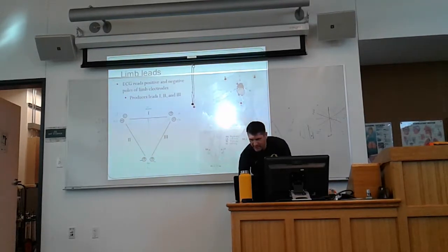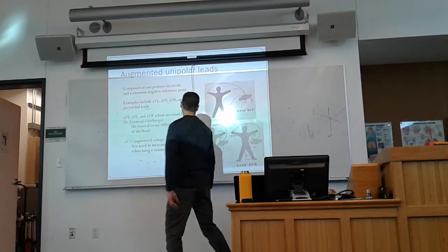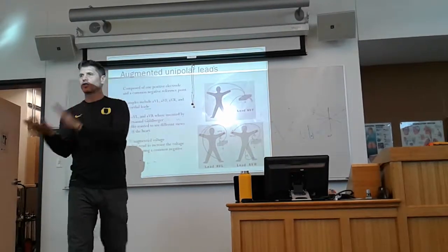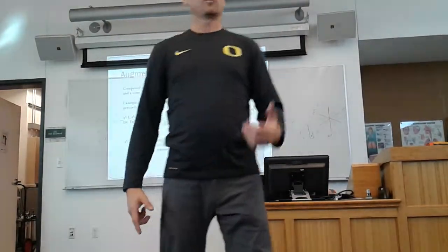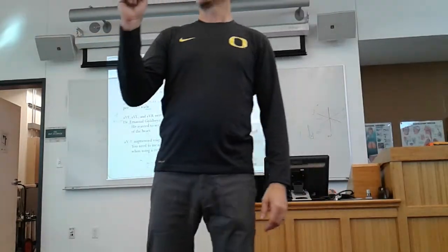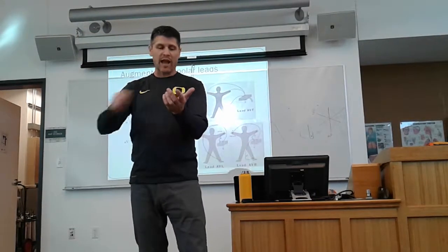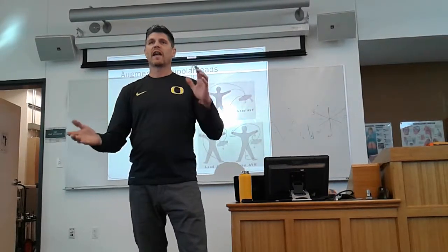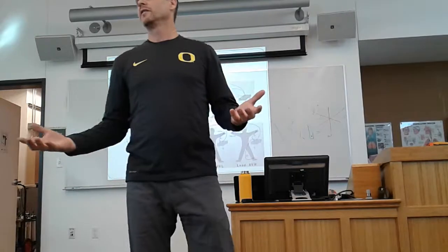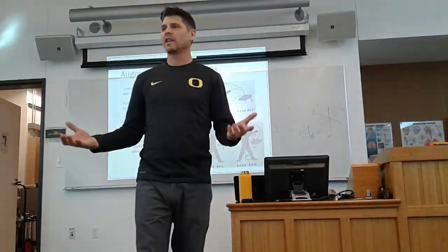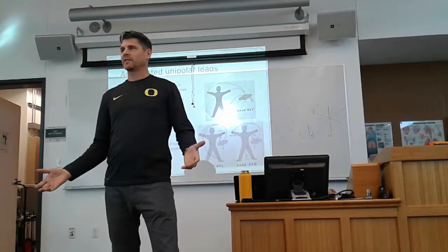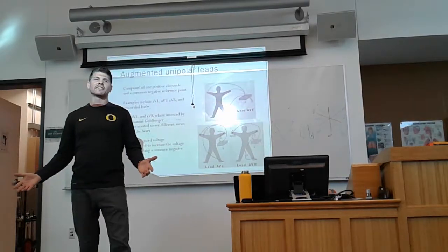And so ideally, in an ideal world, you would do a couple of things. In a complete ideal world, you would put the electrodes on wrists and ankles. If we were really doing it well, we would clean their skin. Then you would take a little bit of sandpaper and sandpaper off their epidermis. Then you would alcohol the area to clean it all off, and then you'd put the electrode there. That would be the research grade quality EKG that you'd be looking for, that wouldn't have any weird artifact or anything in it.